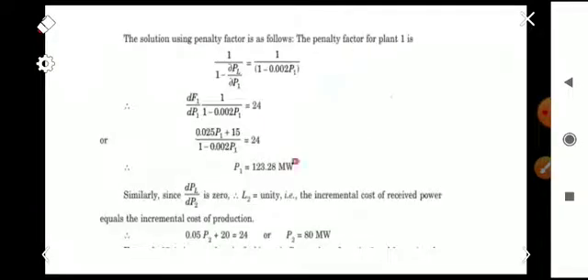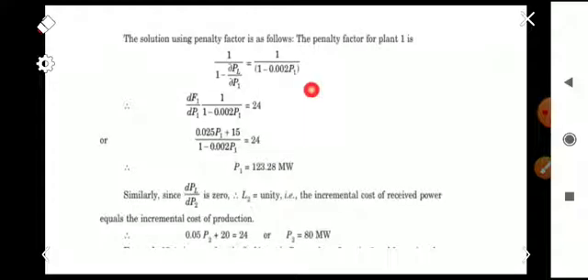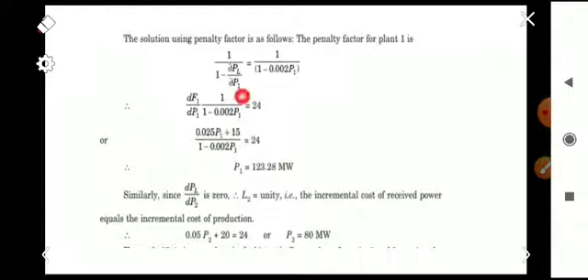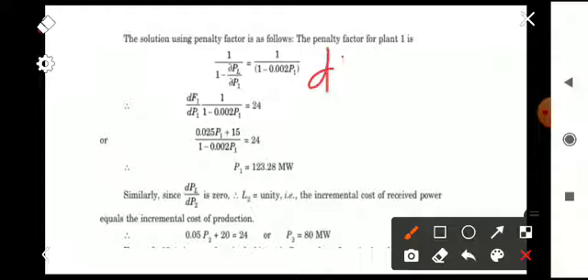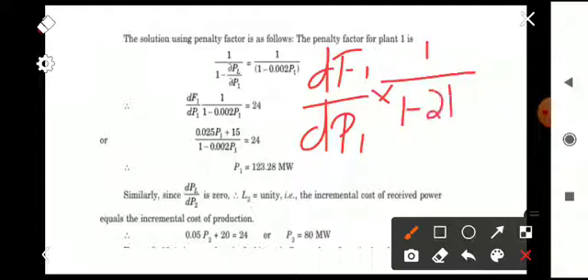The penalty factor for plant 1 is 1/(1 − ∂PL/∂P1) = 1/(1 − 0.002P1). Substituting into the first coordination equation, dF1/dP1 × (1/(1 − ∂PL/∂P1)) = λ, we get the same result: P1 = 123.28 MW.